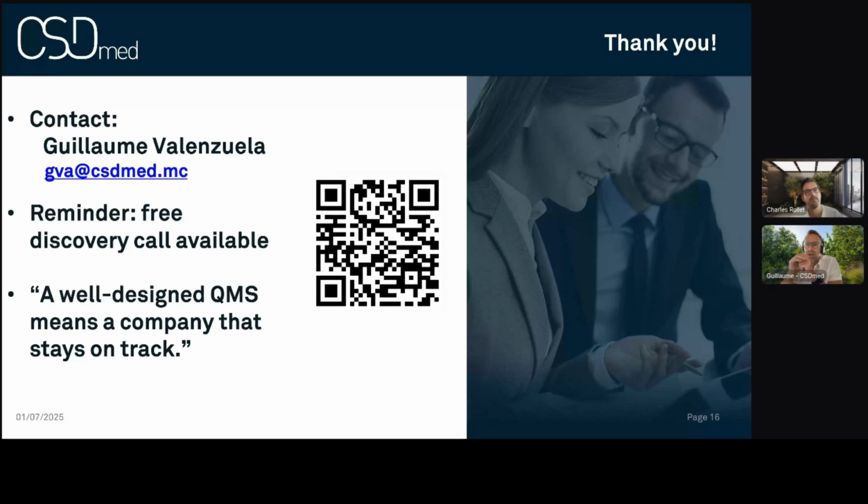So, as I said during the presentation, Article 10.9 says you need a QMS. It's mandatory. You don't need to be certified. Certification is a plus, but you could say, okay, we have a QMS. It's not mandatory to be ISO 13485. You can have your own QMS if you're creative. Go for it. But you may find some problems.